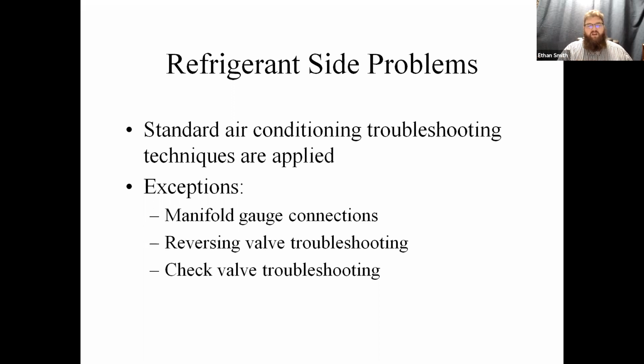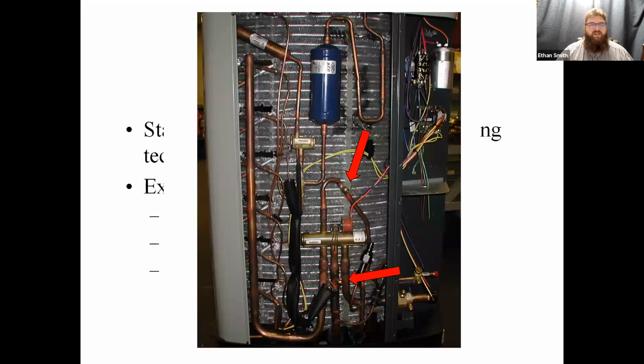Reversing valve troubleshooting we'll talk about, and check valve troubleshooting we'll talk about in just a second. So there are those gauge ports in the Trane units. You just open up that side panel. The reversing valve is outside the coil, and we've got an alternate port for the suction port and an alternate port for the high side port. Just for clarity's sake, guys, this port up here should be the same pressure as this port down here because it is the vapor line in heating mode. That comes straight off the compressor, goes through the reversing valve and out that side, and we've got our vapor pressure port right there.